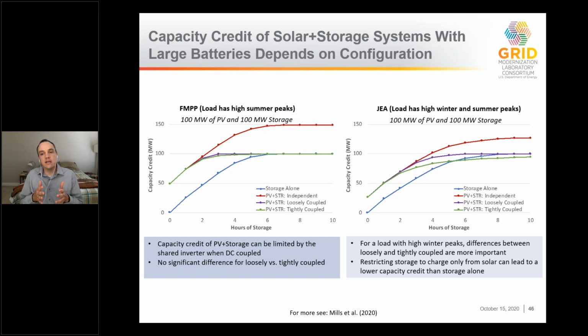If you start to bring these things together with any shared infrastructure, like a shared inverter or a shared point of interconnection limit, as in the green and purple lines, you can run into a situation where your solar is discharging at the same time as your storage, effectively capping the total capacity credit of the solar and storage asset. That's important to keep in mind: such limitations can impose a constraint that limits the flexibility you're able to get out of the storage.